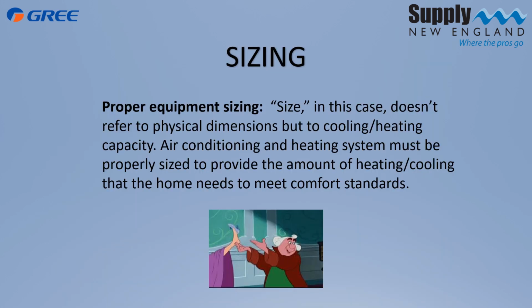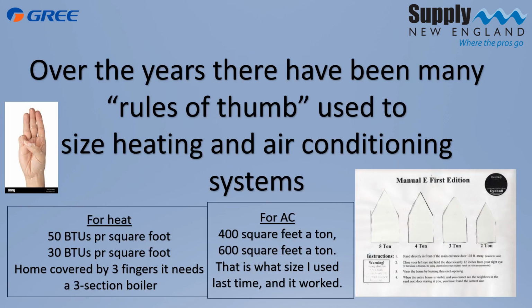Now let's talk sizing. And I'm not talking about the physical dimensions of a unit. I'm talking about the capacity. How much heating and air conditioning can the system provide us in our environment and our home? Over the years, there's been many rules of thumb used to size heating and air conditioning systems. On the heating side, 50 BTUs per square foot, 30 BTUs per square foot, or my favorite is the fingers.